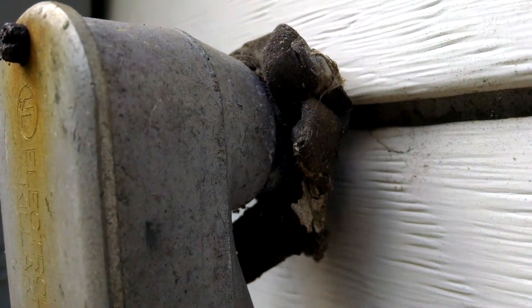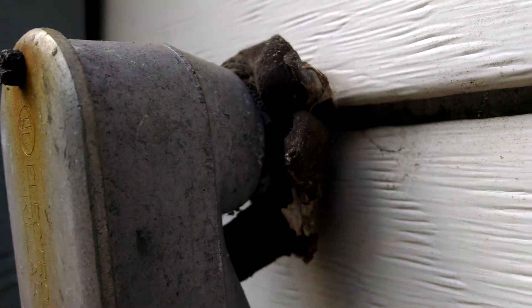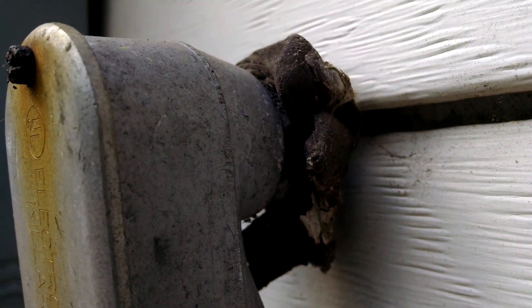More importantly, I wanted to show you — pull that back so you can see the bare wires and see how that's moving. That means anytime the wind blows, those wires are rubbing up against there, and this here is a major electrical issue.